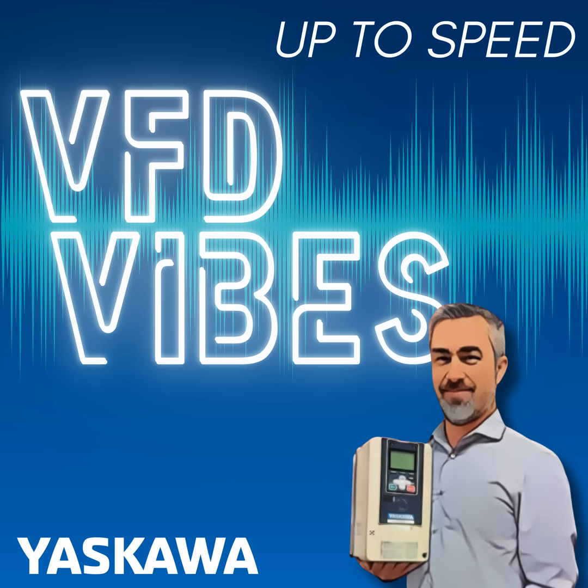The other thing that really made me perk up was just the thought of new electronics. In my career, I've done a lot with inputs and outputs, signals to PLCs, as well as industrial networks. And what we are always trying to do is increase speed, increase throughput. What tends to happen is your wire sizes shrink. You have more twisted pairs. The field bus networks of a couple decades ago were extremely robust. They were also extremely slow. So as we have new instrumentation that's now sending 100 pieces of data instead of 10, and the network is much faster, it's much more sensitive to these types of transients in our power system.